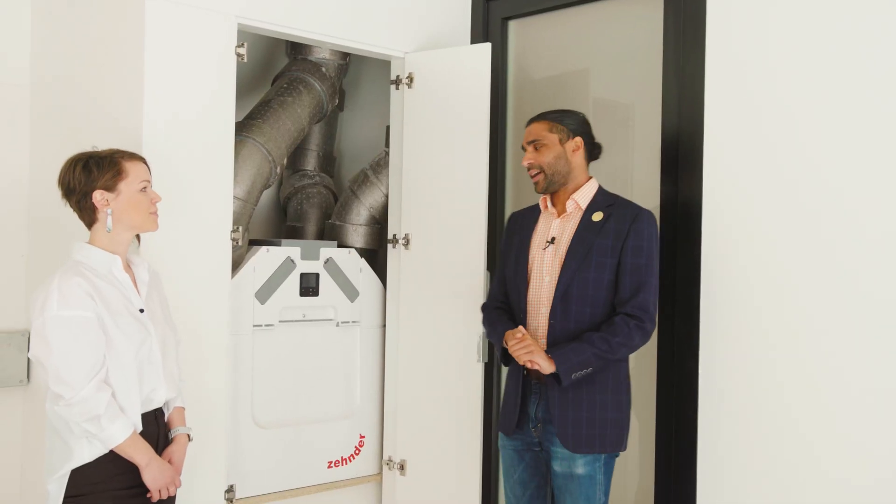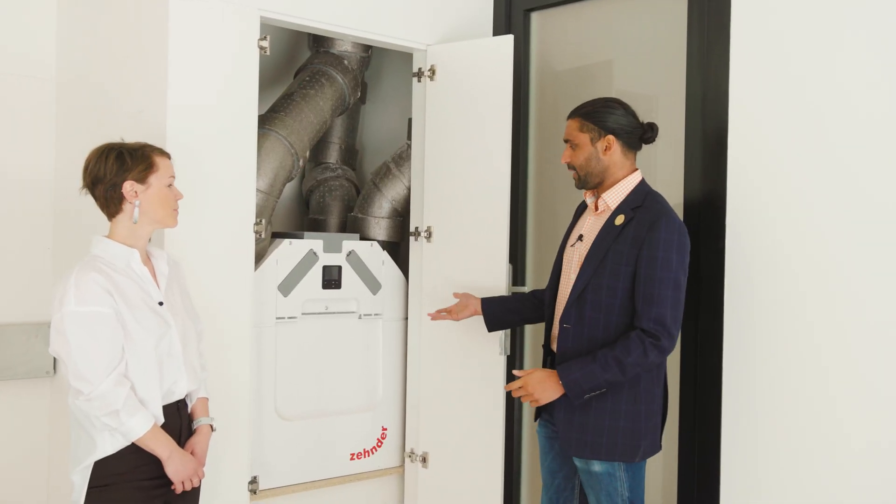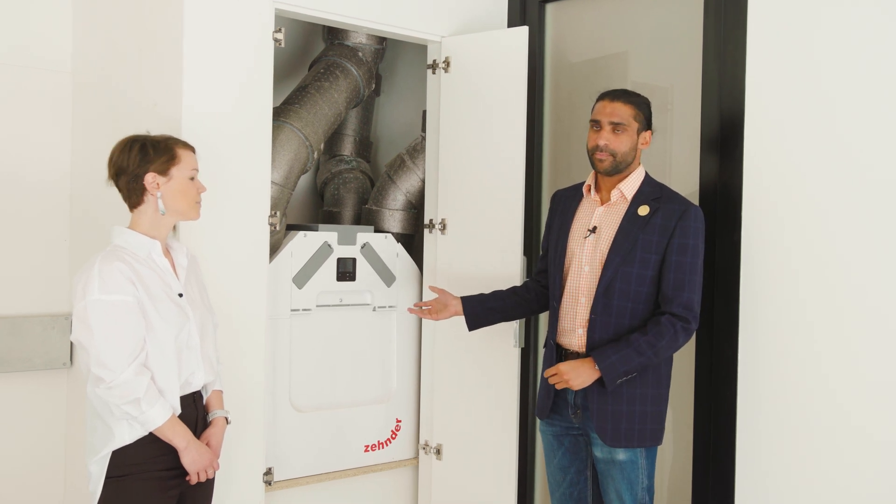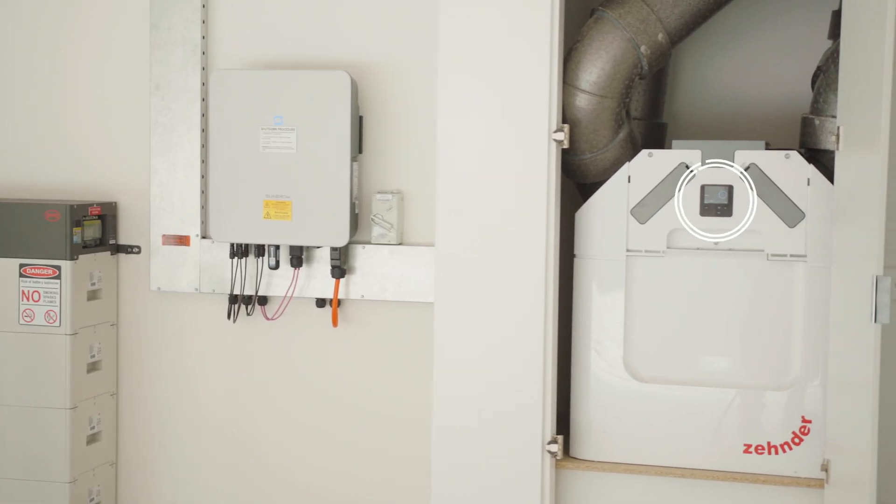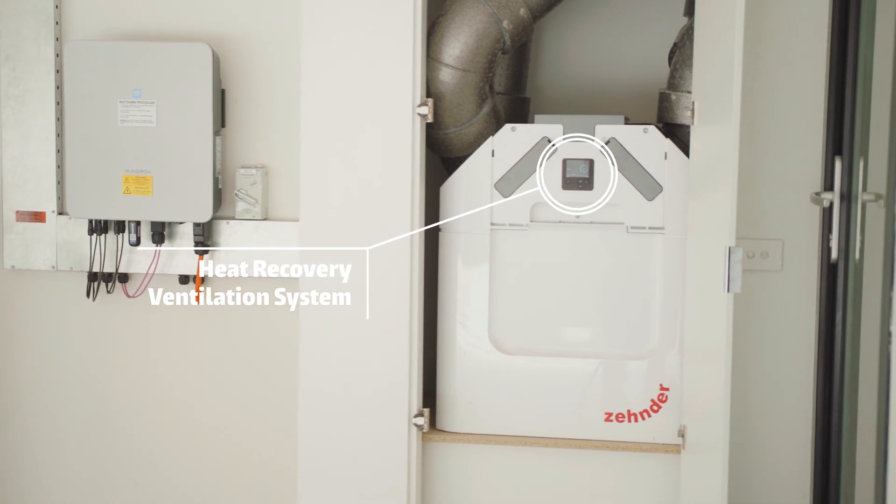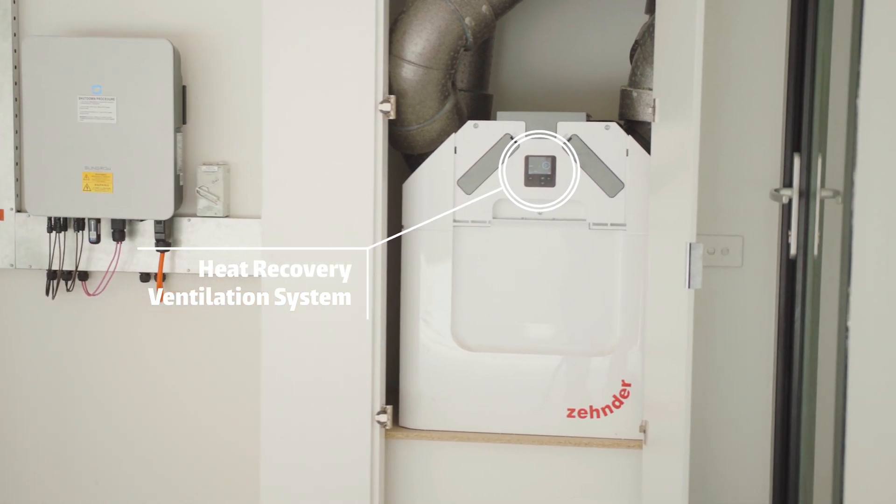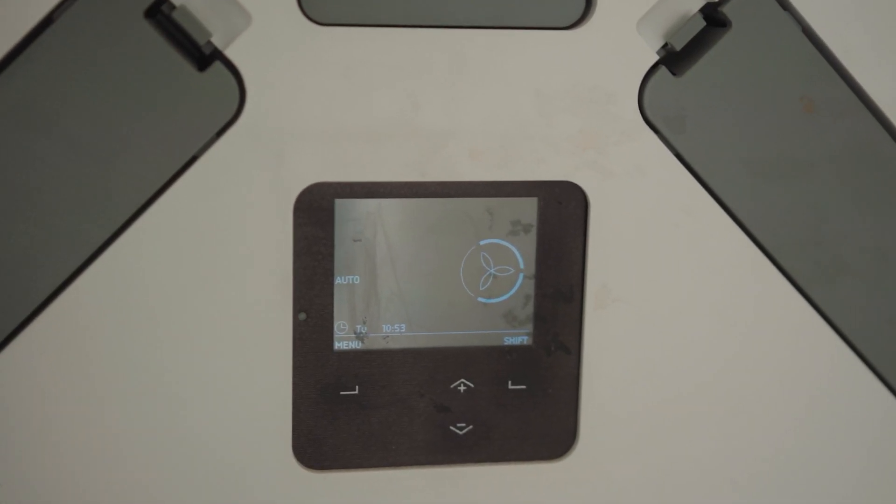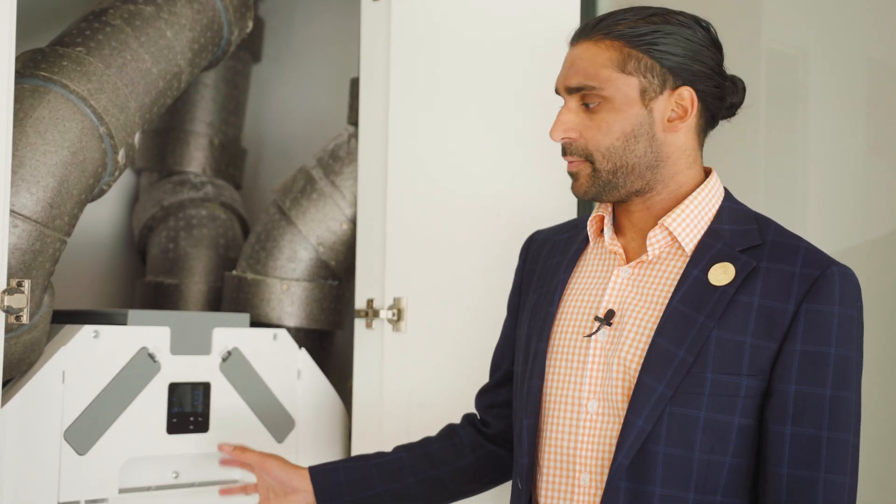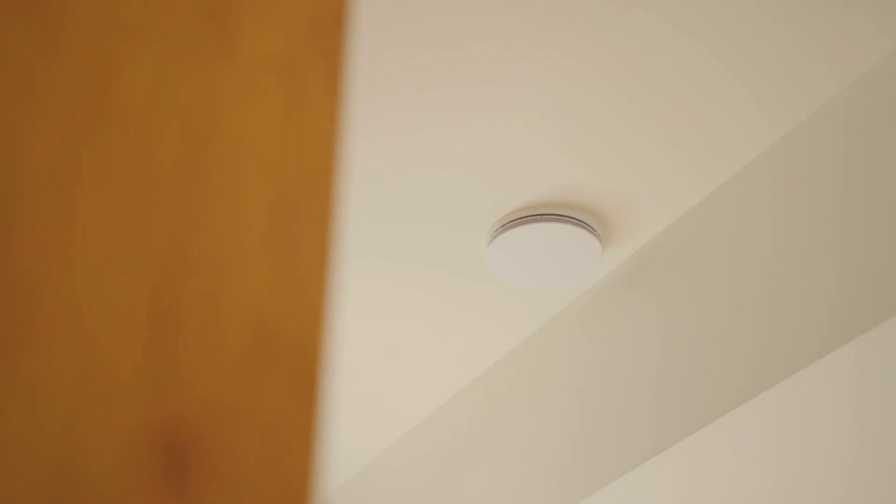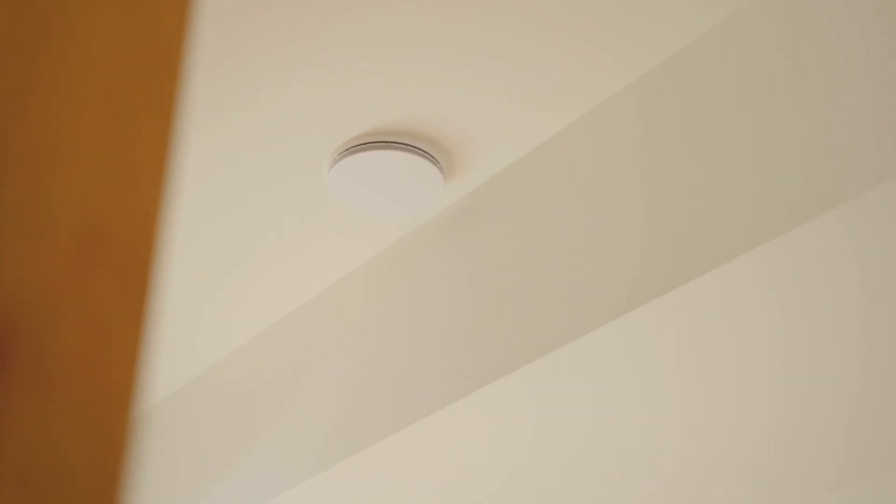Here we have the heat recovery ventilation system, also known as HRV system. This is really critical for all Passive House houses. It allows fresh air to come into the house without significant loss of energy. Inside this HRV system are a couple of fans and a heat exchanger. All the air being exhausted from the house passes through this and pre-cools or preheats the air coming into the house. Through this system we save about 90% of the energy that would normally be lost from exhaust.